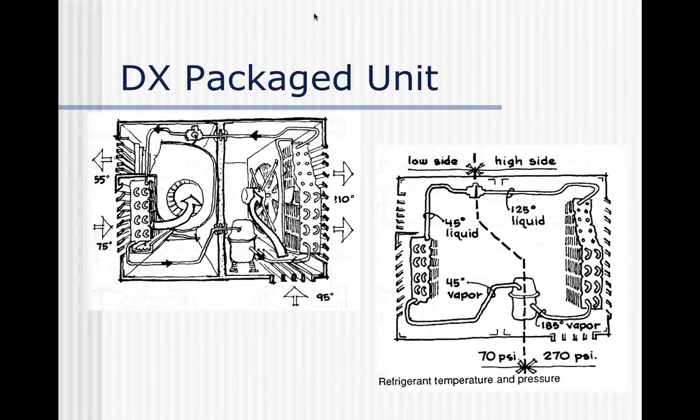So they've come down in cost, but in order to come down in cost, they made some compromises on the design. Instead of an expansion valve, it's got a little capillary tube. The freon tube comes along, and just before it gets to the coil, it reduces into a tiny little tube, right? That only lets a tiny bit of freon go through. So what happens is freon's always going through there into the coil, and the compressor shuts off and stops creating more liquid freon that'll expand. So it's really the compressor that is the boss now rather than that meter. It's always metered in there at a slow rate until you stop cooling it.